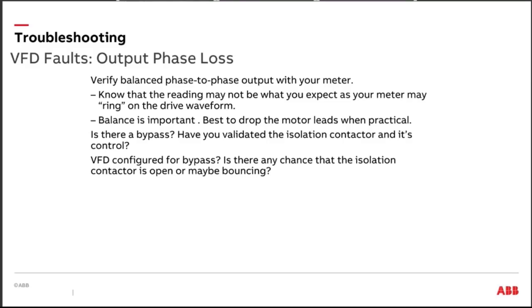A couple times I've actually seen a couple problems with this. It's not uncommon that we might lose a control fuse and we're not able to bring the isolation contactor in. And it all depends on how your control circuit's made up. And we might get an output phase loss, okay? I've also seen that isolation contactor bounce. And that typically causes an instantaneous overcurrent trip if that contactor bounces any at all.